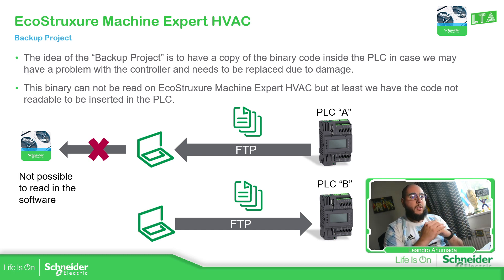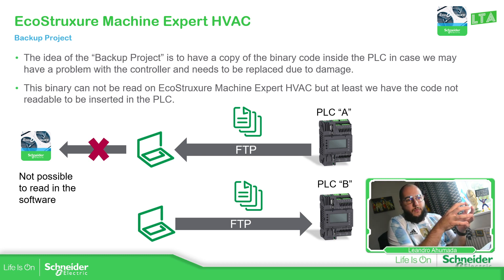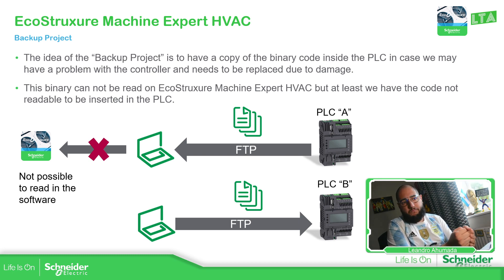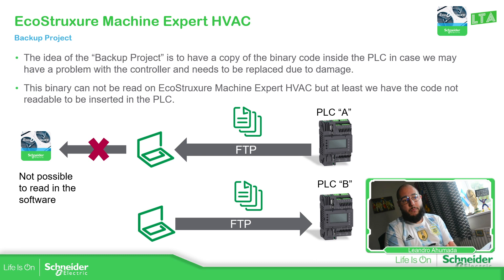So let's go to the presentation to see how we can make a backup of the binary code and variables, in case we need a hard copy to replace a controller and don't have the original code. The idea is: I have PLC-A and PLC-B, and using FTP I'll grab all the binary code from PLC-A and send it to PLC-B to have the same application.